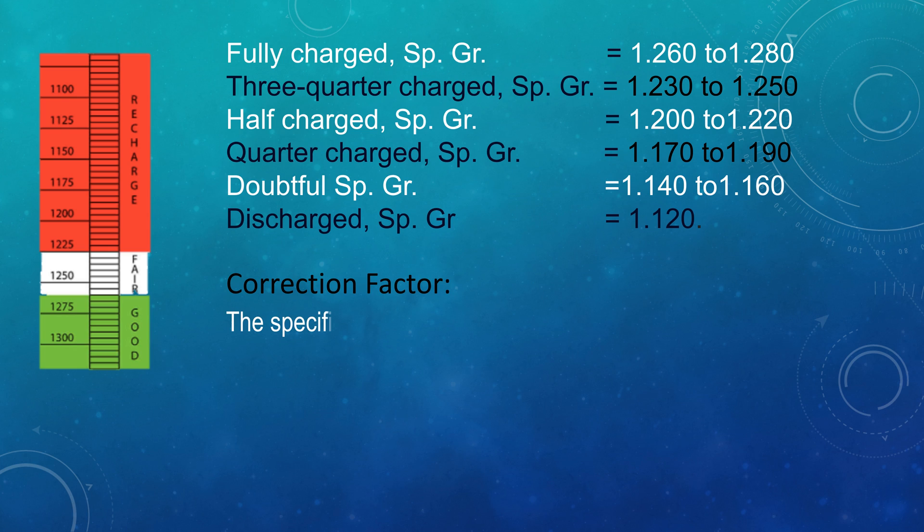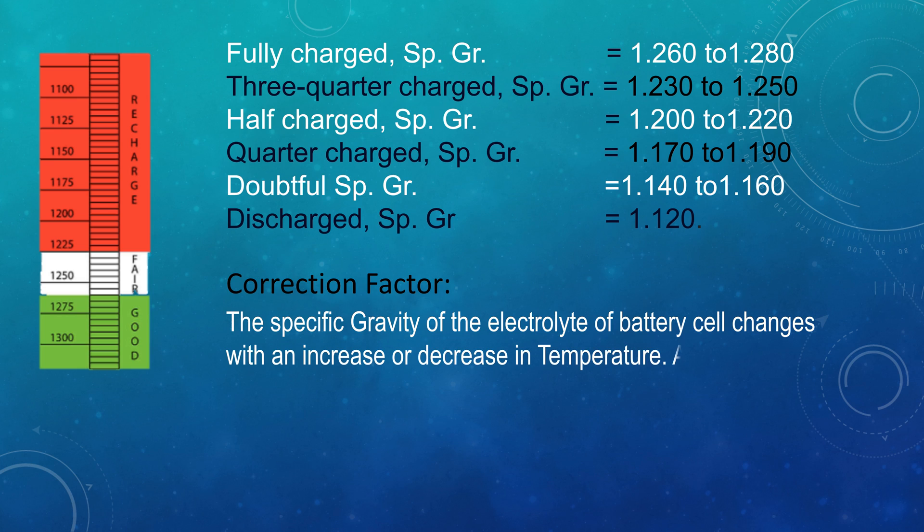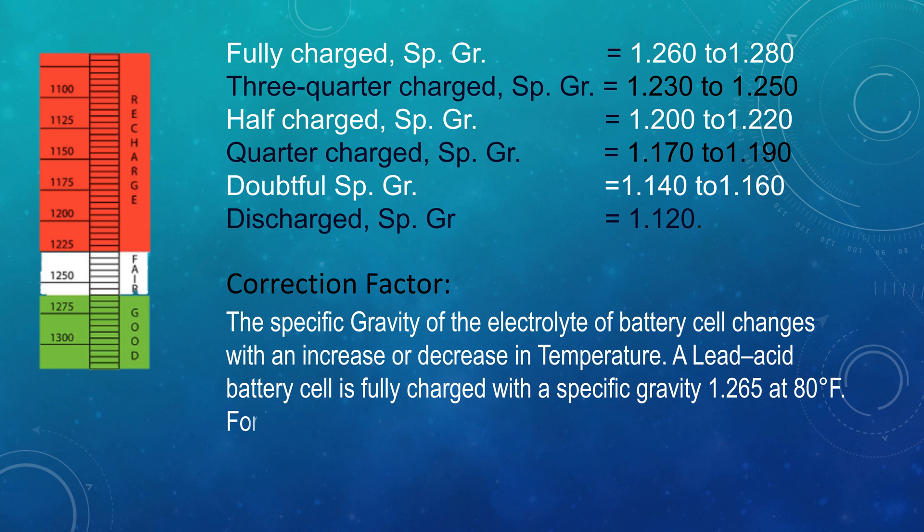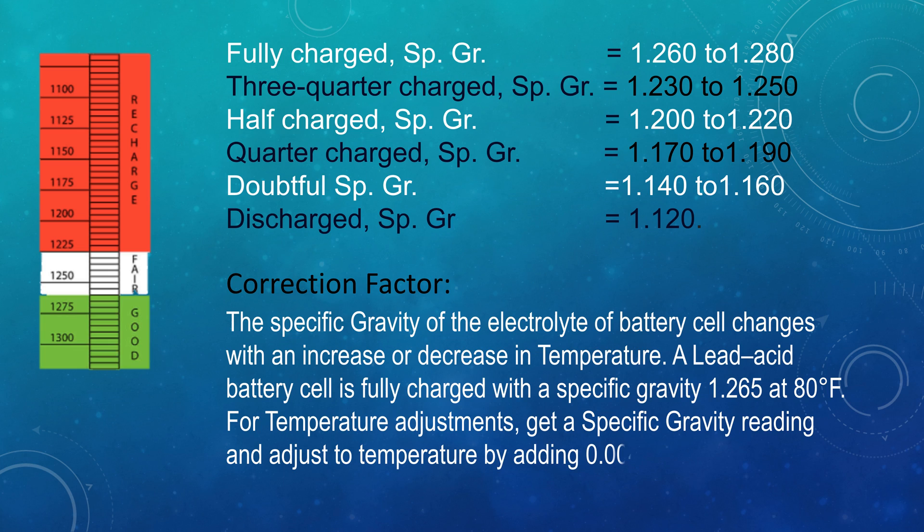Correction factor: The specific gravity of the electrolyte of battery cell changes with an increase or decrease in temperature. A lead acid battery cell is fully charged with specific gravity 1.265 at 80 degree Fahrenheit. For temperature adjustment, get a specific gravity reading and adjust to temperature by adding 0.004 for every 10 degree Fahrenheit above 80 degree Fahrenheit and subtracting 0.004 for every 10 degree Fahrenheit below 80 degree Fahrenheit.